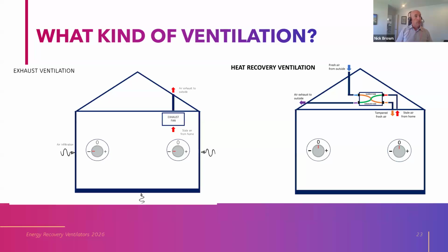Heat recovery ventilation, or ERVs, are a balanced ventilation system in a box, pulling stale air out, that's the purple arrow shown up in the attic, and pulling fresh air in from somewhere else, swapping the heat in the two streams, then distributing that tempered fresh air where you want it inside the house, and pulling stale air from where you want to pull it. Pressure is balanced, and you get the benefit of heat recovery. With an ERV, you're not just swapping heat of those two streams, you're also swapping moisture, which allows you to keep humidity in our dry climate in the house. That's generally seen as one of the benefits of ERVs over HRVs, which just swap heat.